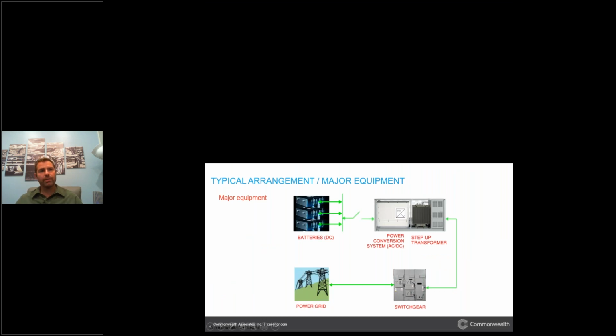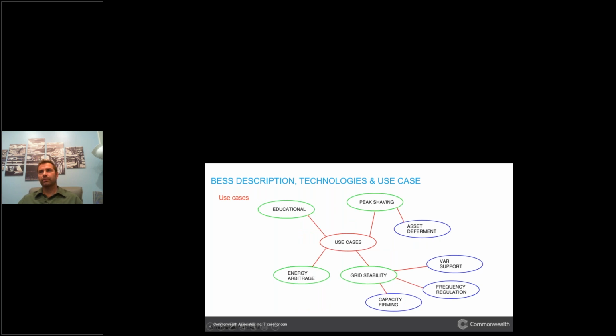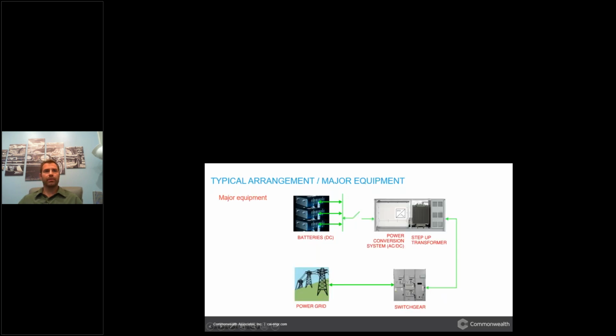So what are all the major pieces of equipment for a project to go around the loop? Left is a battery cell, or actually I'm showing 3 battery cells. The cells, which are maybe the size of a briefcase, are wired together within a rack. I'm showing 3, but usually on a utility scale project there are going to be 10 to 15 cells in a rack, and the rack is overall the size of a small refrigerator. And then multiple racks are connected together within the container or enclosure. The racks are then wired to the inverter converter. Go back.